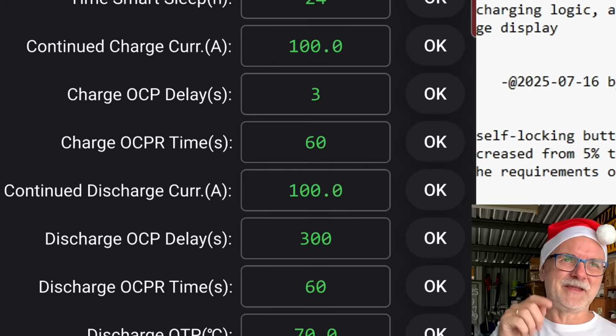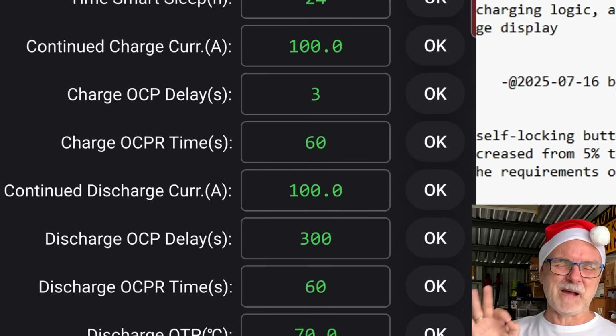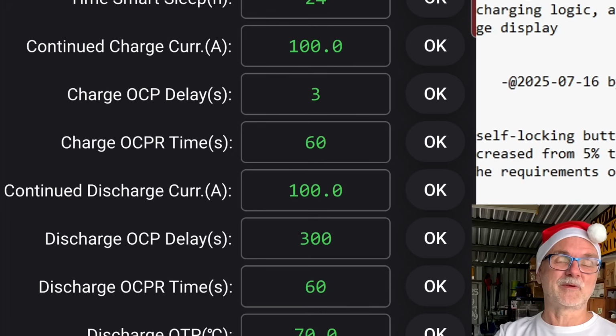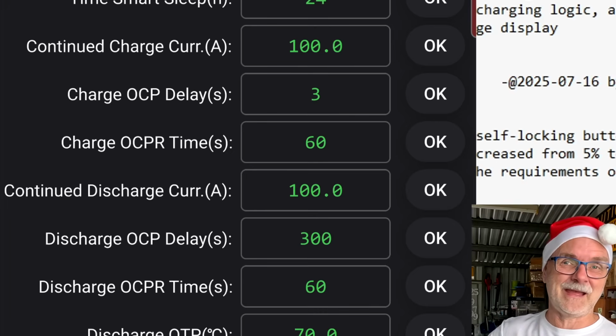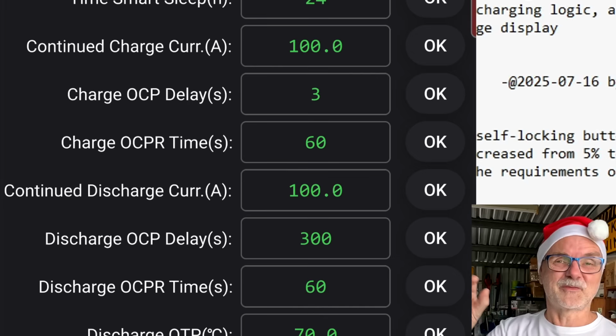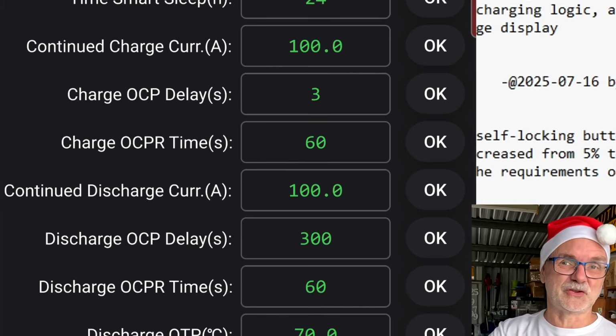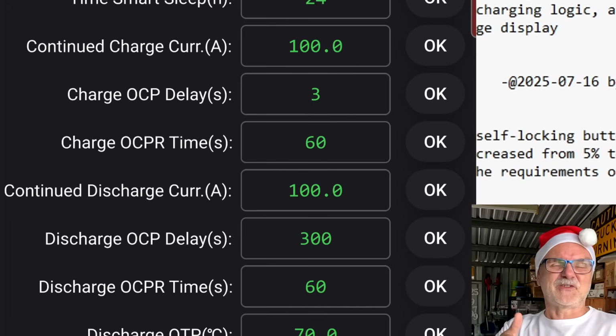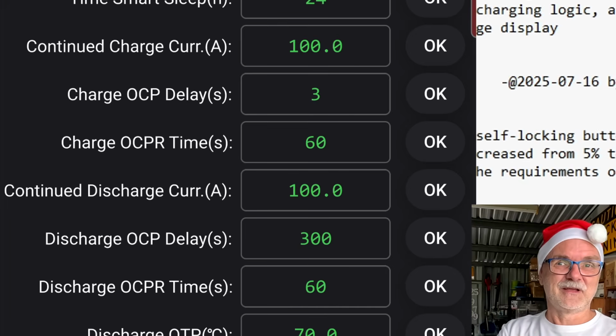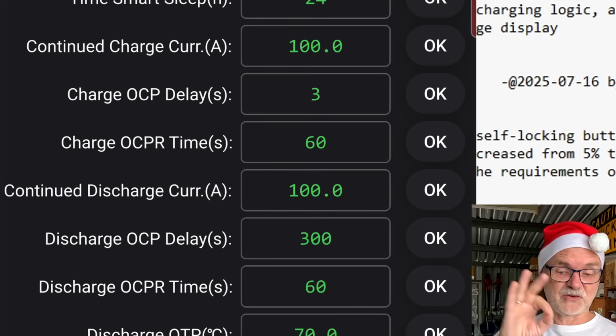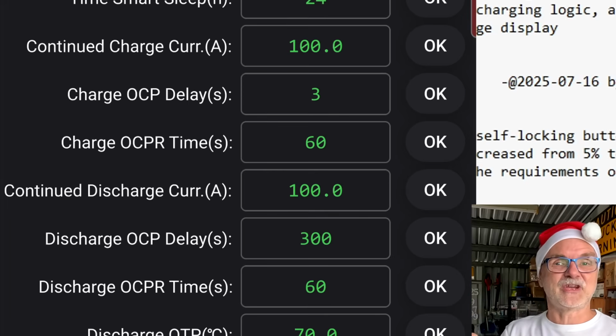And until this update, there was a 5% margin. That means when we set 100 amps in the BMS, it would report only 95 amps to the inverter. So there was a bit of a gap, allowing some surges, yeah? You don't want to trigger your overcurrent protection all the time, or your discharge current protection, just because you're hitting these 100 amps. So it was a bit of a reduced information going to your inverter, which is fine, yeah? And this has now changed.